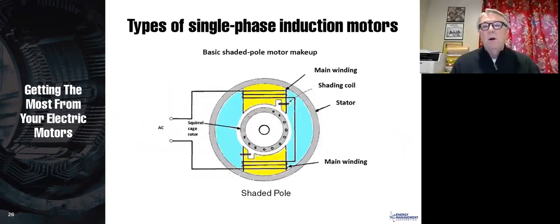And we have one more, that's a shaded pole. Shaded pole doesn't have the auxiliary winding or the capacitors, but we shade part of this pole, and that gives us a little bit of rotating flux. Now, shaded poles do not have very good starting torque or very good running efficiency or very good power factor, but they're cheap and they're reliable. So if you have something, let's say a little fan in a microwave, maybe you would choose to go with a shaded pole because it's in a place where it's hard to maintain, and they're cheap and reliable and they don't have capacitors to fail.